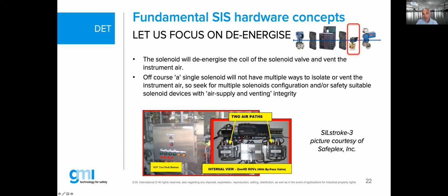As you can see over here, and I took here the courtesy of a friend of mine in the industry, he is presenting here what is called a SILstroke-3 picture, which is a 2 out of 4. As you can recognize maybe on this picture, you see here on the left-hand side 2 solenoids and on the right-hand side 2 solenoids, and both are being fed back into this PLC over here. They do continuous block and bleed. They are measured, and that is used to replace this one single solenoid. That's actually been used here as a practical example in a box.